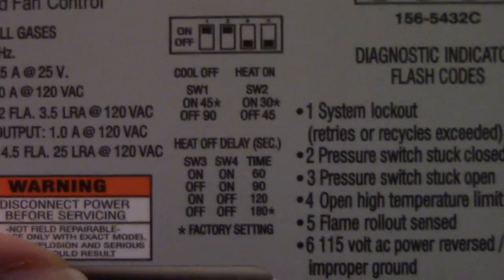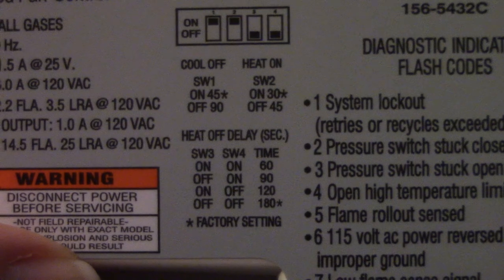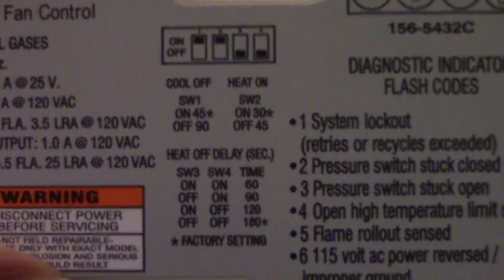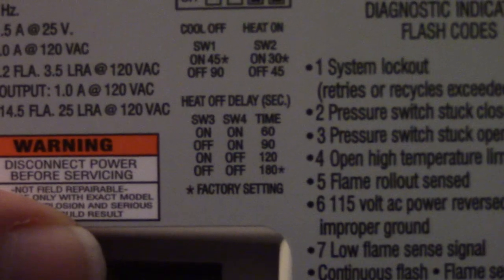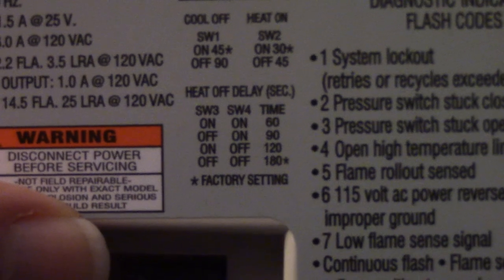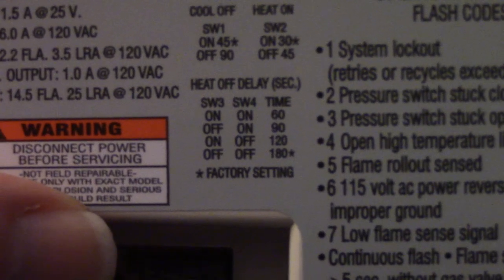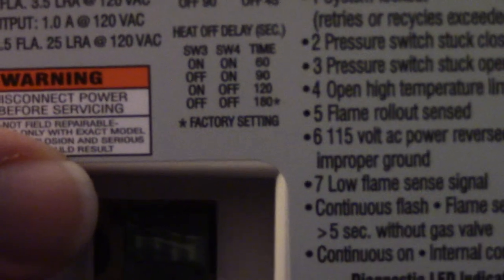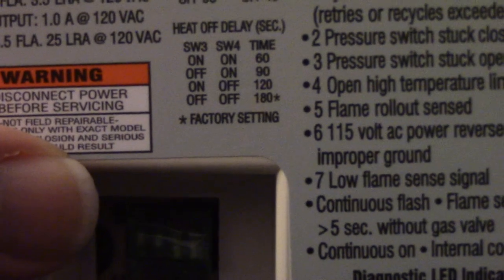You have switch 3 and 4 you're going to use, as it shows on this one. If they're both up, it's 60 seconds. Switch 3 off, switch 4 on, 90. And if both switches are off, it's 180 seconds.